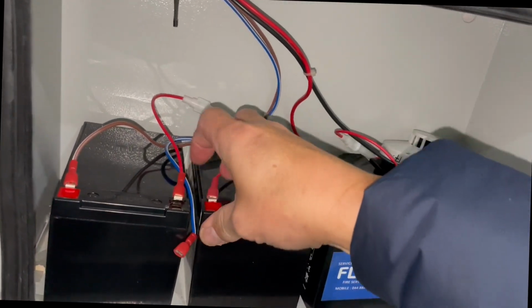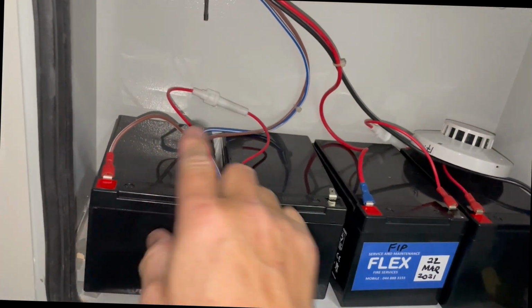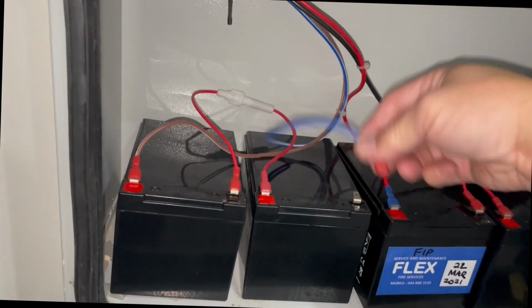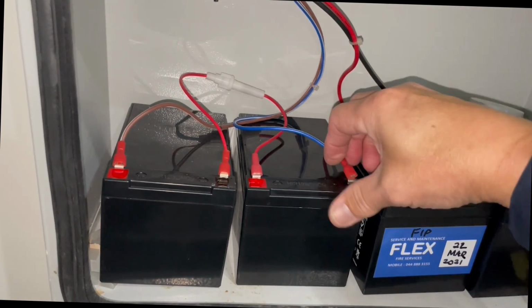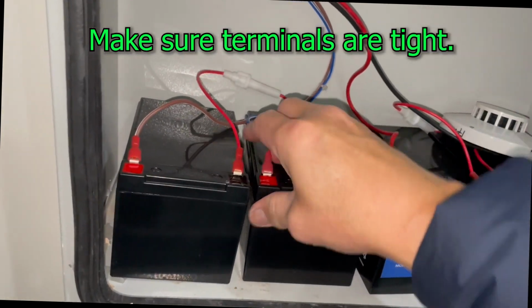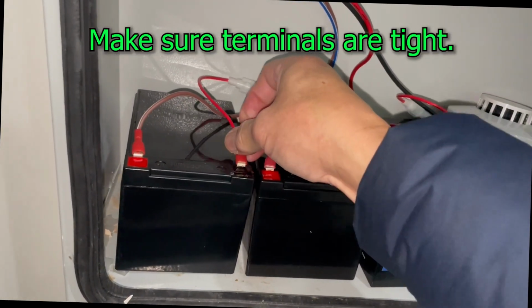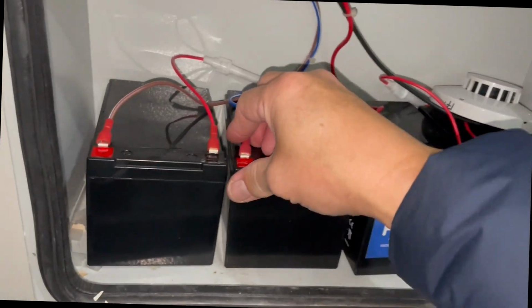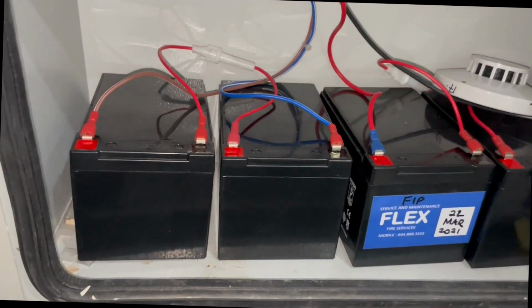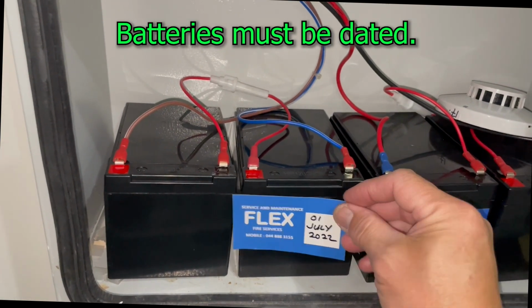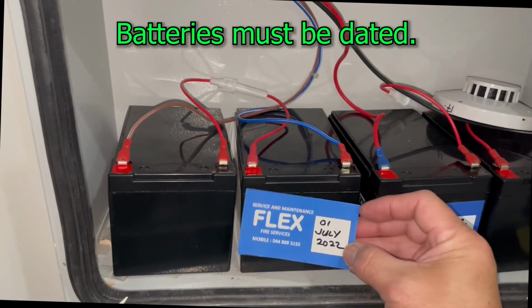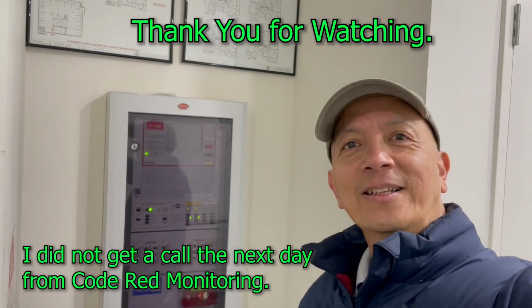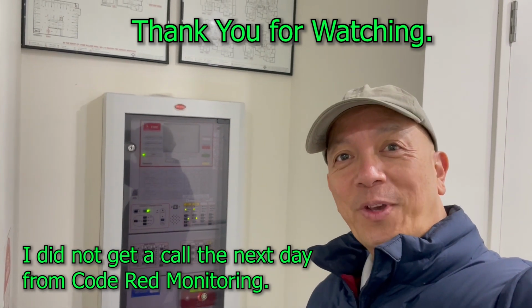Alright. So the batteries will be in series, 12 plus 12 equals 24 volts. And this one is your negative. All done. Alright. And the most important of all, check that everything is properly tight. Right? And we're going to put the sticker with the date today. Alright, all good? So that's it. We were able to fix the problem.